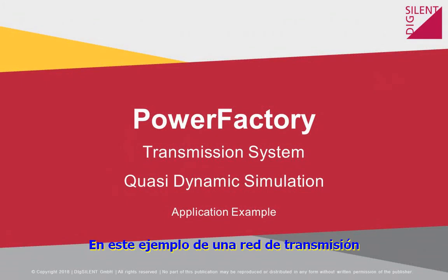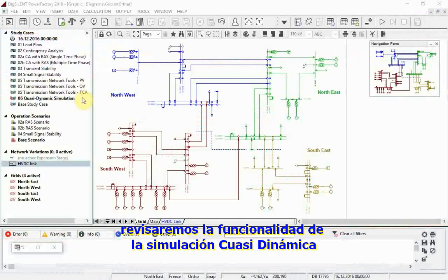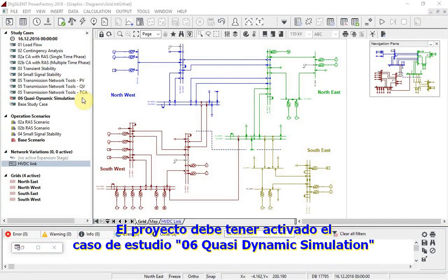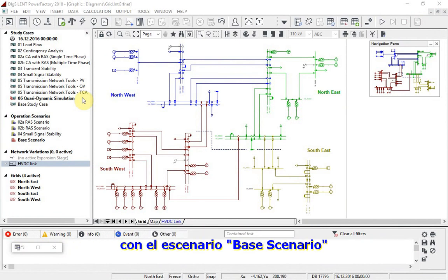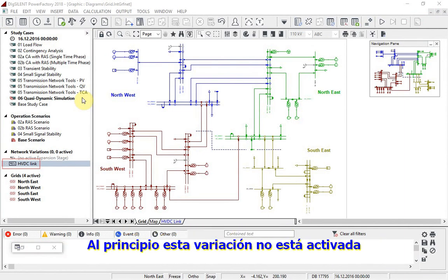In this transmission network example, we will look at the quasi-dynamic simulation functionality. The project should have study case 06 quasi-dynamic simulation active, together with the base scenario. Note also that there is a network variation called HVDC link. To start with, this variation is not activated.